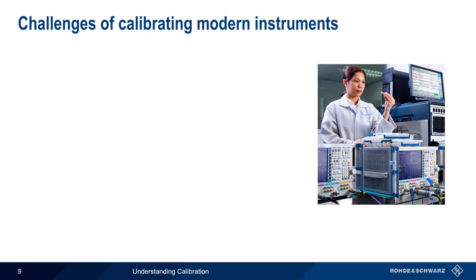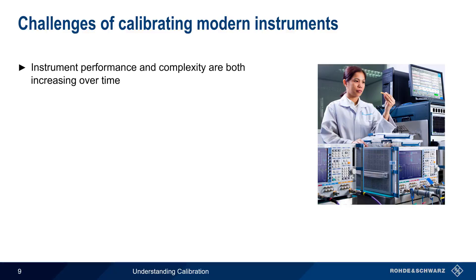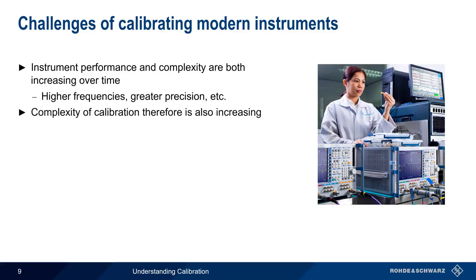Measurement uncertainty becomes even more critical when it comes to calibrating modern instruments. Over time, both the performance and the complexity of test and measurement instruments have been rapidly increasing. For example, newer technologies often operate at higher frequencies and/or require more precise modulation accuracy compared to even a decade ago. Calibrating the instruments used in developing and manufacturing these technologies has therefore also become more complex and demanding. The margin of error, or the acceptable measurement uncertainty, has become lower, and the risks and costs arising from a substandard calibration have become much higher.